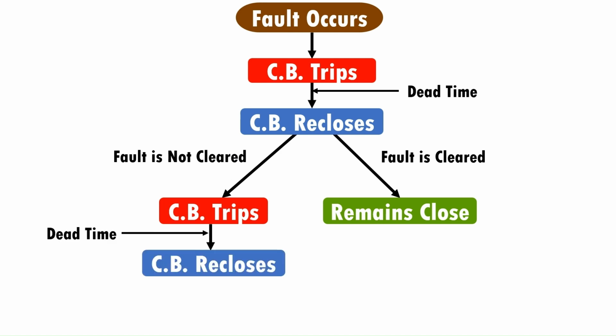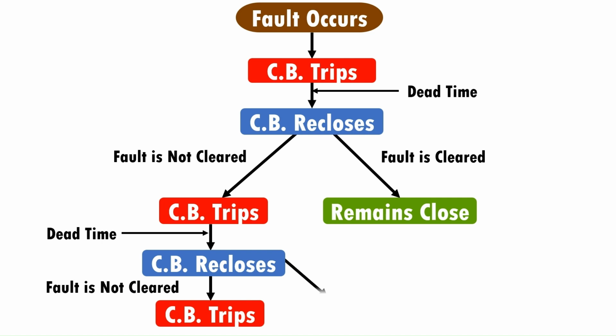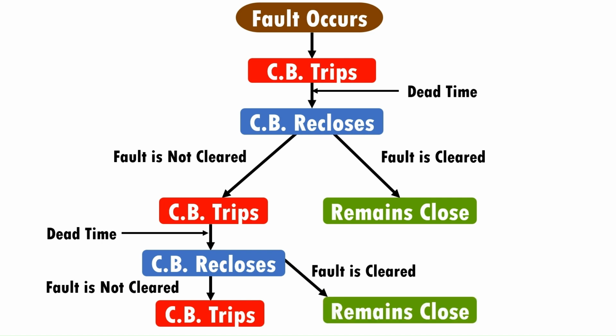Again, the recloser waits for some predetermined time and closes the contacts of the circuit breaker. Now this time, if the fault is cleared, then the contacts remain in the closed position. But if the fault is not cleared, then the circuit breaker contacts will open again and remain open until manual reset, and it is considered a permanent fault. The duty cycle of an auto recloser is expressed as O, 0.3 seconds, CO, 3 minutes, CO. Here O means open and CO means close-open.